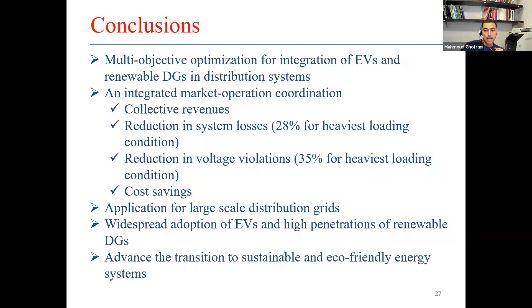So this is the project that, like I said, was concluded, and then there has been some other work in progress. What we've been trying to do is come up with an alternative approach to optimize the system, because the problem with the capacitor optimization is that you would have to put all this money to buy the capacitor and then to maintain and operate the capacitor, right? And there could also be some transient stability issues associated with the capacitor operation. So in order to not have to deal with those problems, we are looking into an alternative approach, which is called distribution system reconfiguration optimization. So basically we are trying to close some of the normally open switches within the distribution system, and also open some of the normally closed switches that exist within the distribution grid.